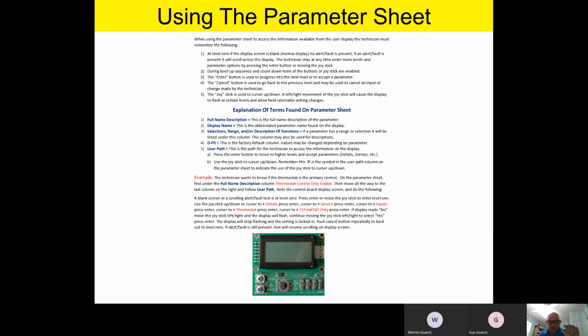And then I'm going to use my cursor up and down to find where it says service. And once it highlights service, I poke enter. And then I'm going to cursor up and down to inputs, press enter. And then I'm going to cursor to thermostat, press enter, and then find the parameter that says thermostat only enable, or thermostat only. And I press enter.